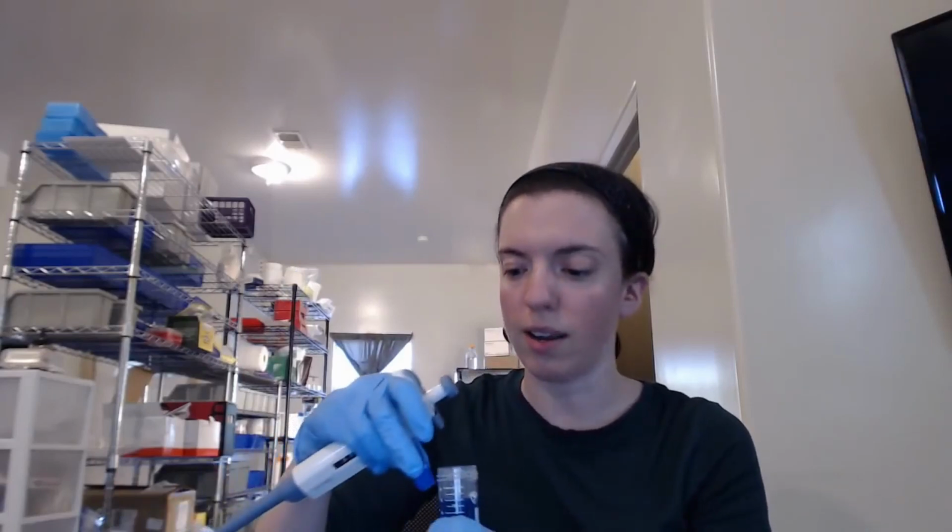Once a year, you want to calibrate your pipettes. I believe there's instructions in there on how to do it. Basically, you're using the density of water and you have a scale and you weigh out the volume to make sure that it's accurate. And if you have more questions about that, go ahead and ask that in the Google Classroom and we can go over that a bit more.